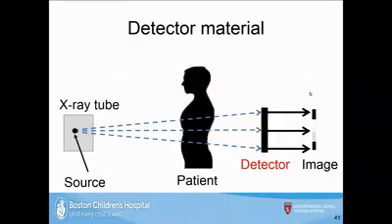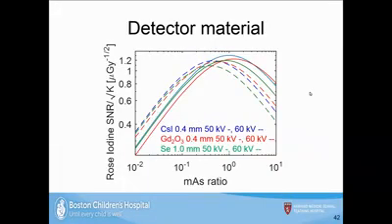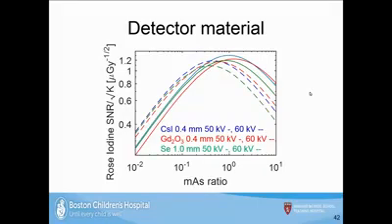Regarding detector material — detectors are not only CsI-based but also gadolinium-based or selenium-based. Plotting Rose SNR per root air kerma as a function of mAs ratio for these three common detector materials, there is no significant difference in SNR between them. Therefore, the same optimization approach applies across different detector materials, and if you pick the optimal mAs ratio for CsI, it will be near-optimal for gadolinium or selenium as well.